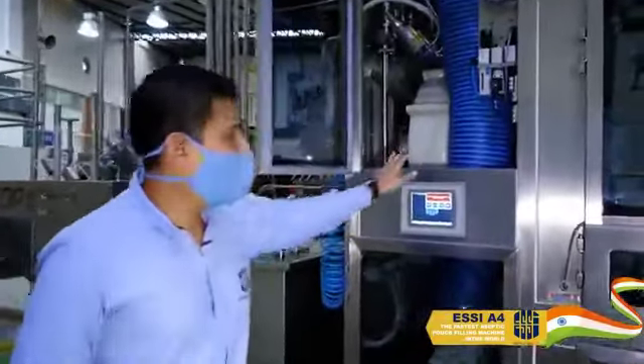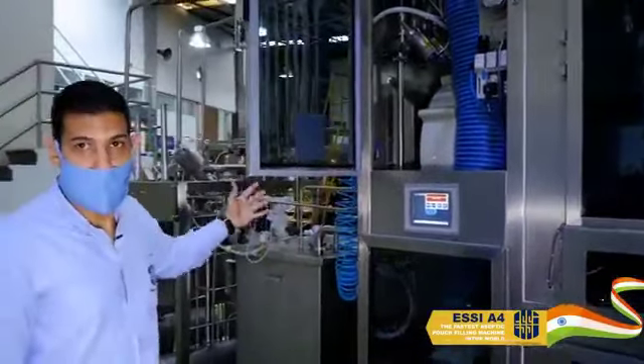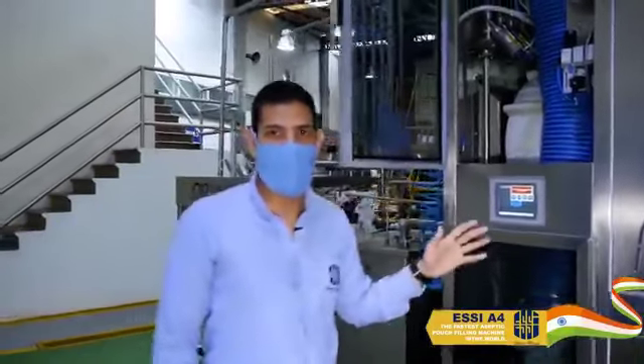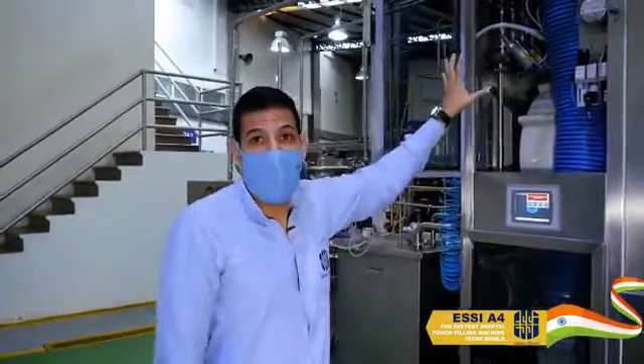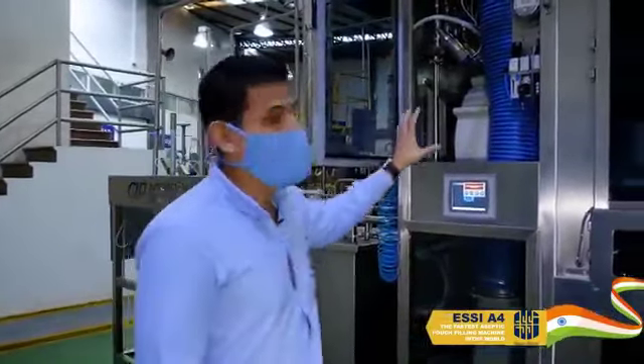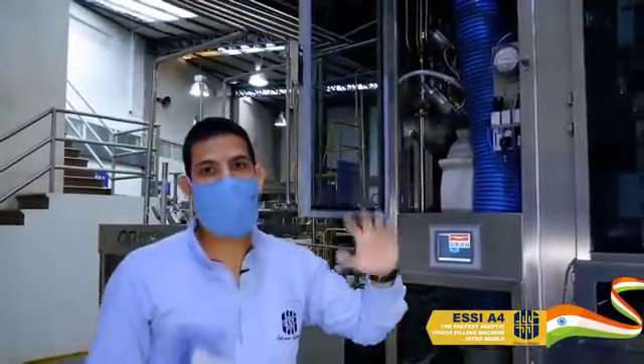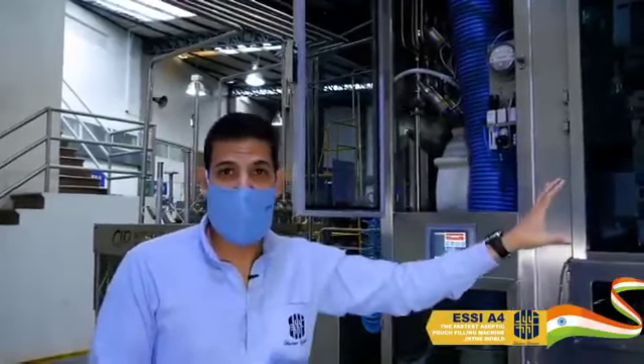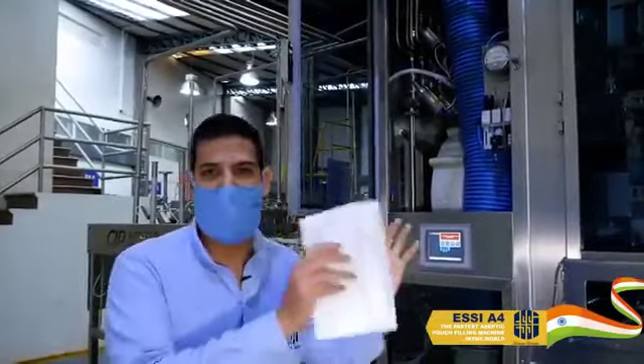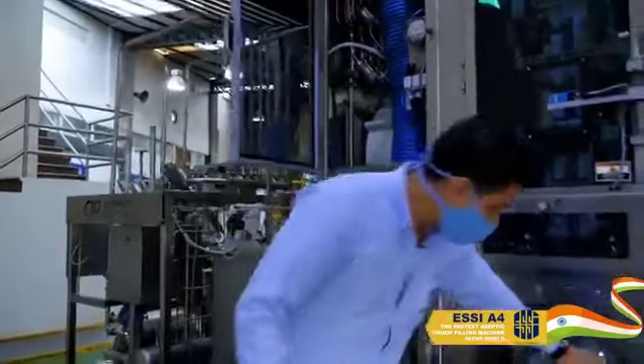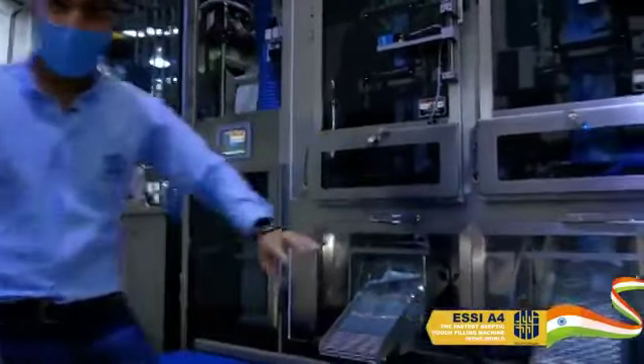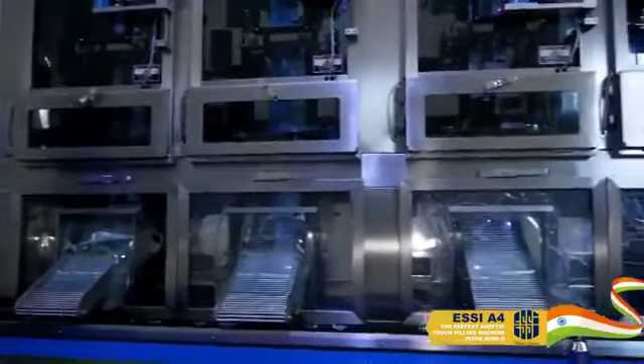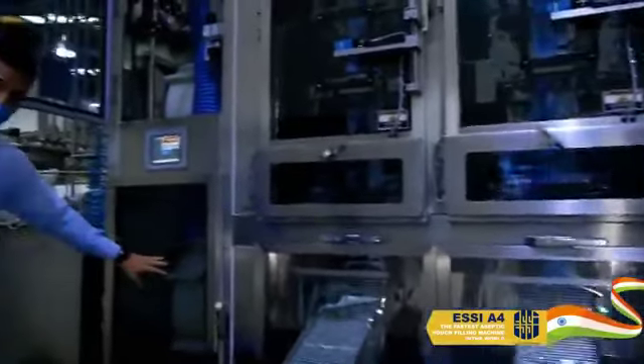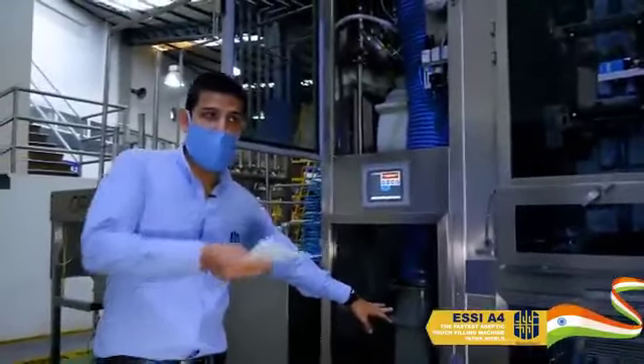We have an inlet blower, and from here it takes the air from the outside, doing a pre-filter of 60%, and after that it goes to the HEPA filter. In the HEPA filter, you reduce the population of the air by 99.999%, and the air is heated up to 40 to 45 degrees. Why is that? Because at this kind of temperature, the peroxide inside of the machine has a greater effect for the sterilization of the cabin. And in the upper part there are some windows, and from that part it takes the excess of air, and from this blower you can take out the excess of air that is in the cabin.